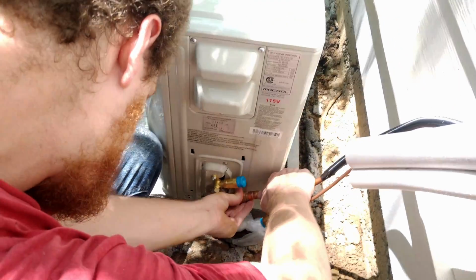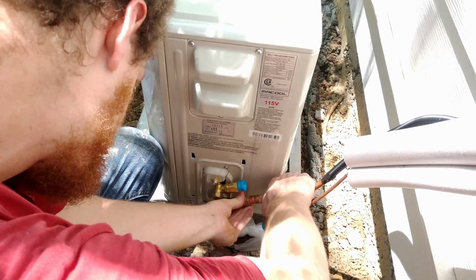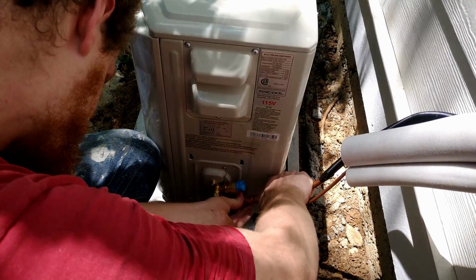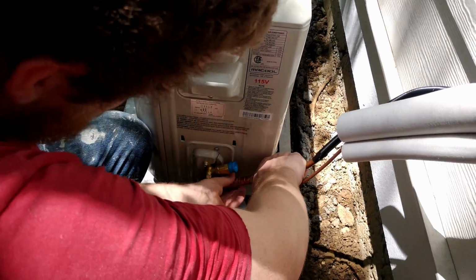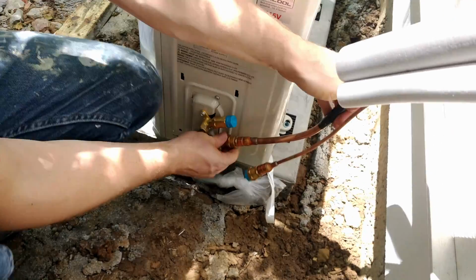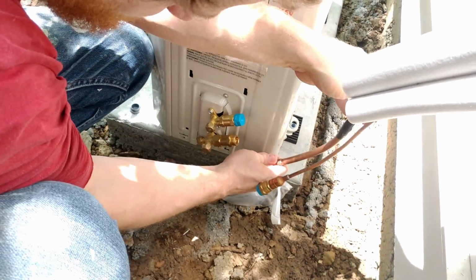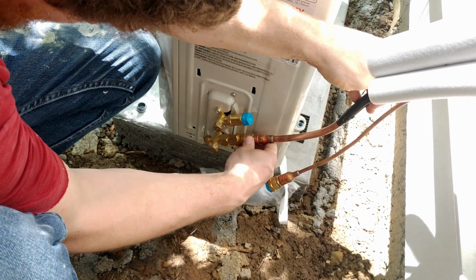But after talking to another HVAC contractor, he seems to think that when we installed the new condenser, the line set probably got dirty, and that contamination in the line set is causing all the problems with the refrigerant. He said once contamination, dirt, whatever, gets inside the line set and starts circulating through the system, it causes all sorts of problems.